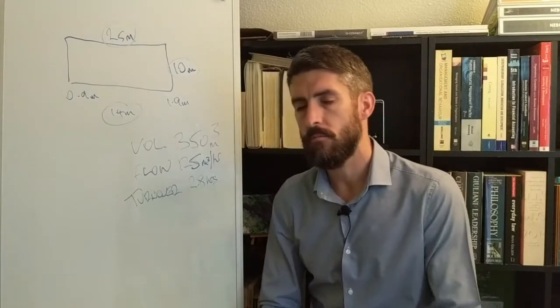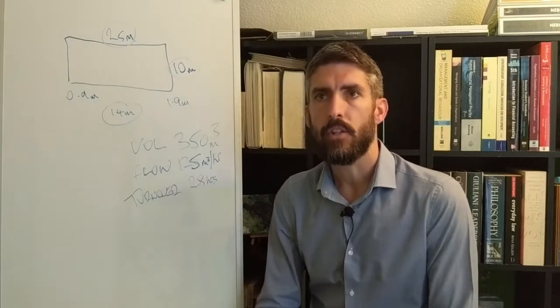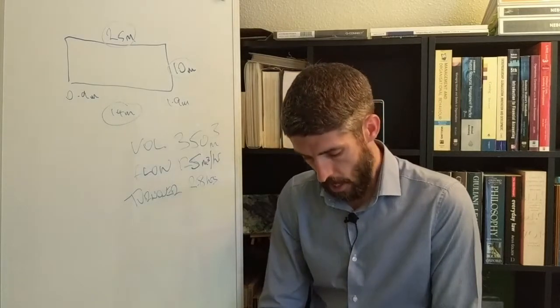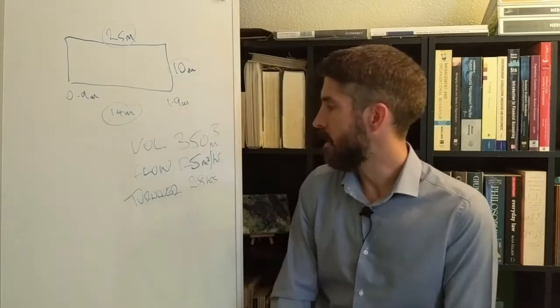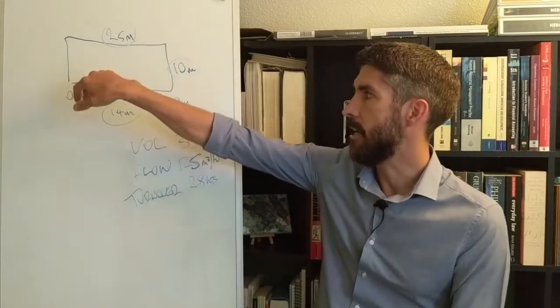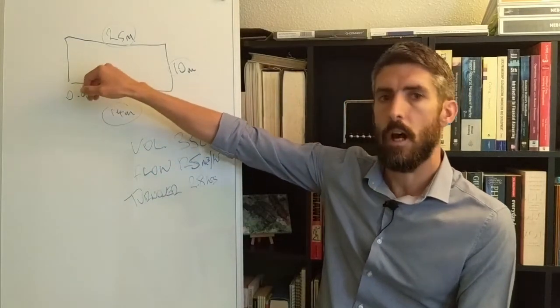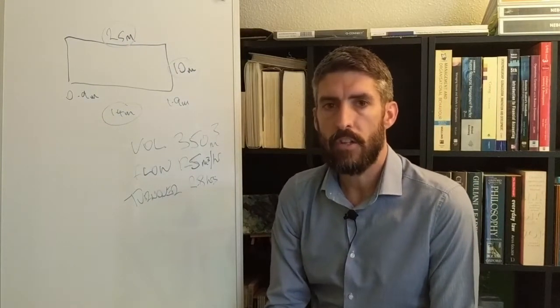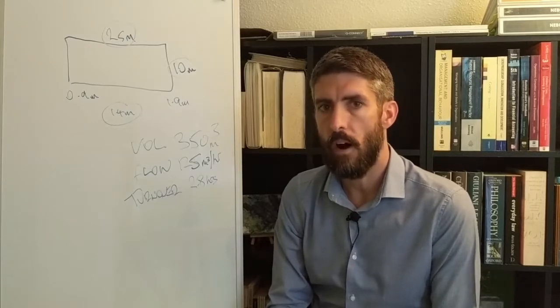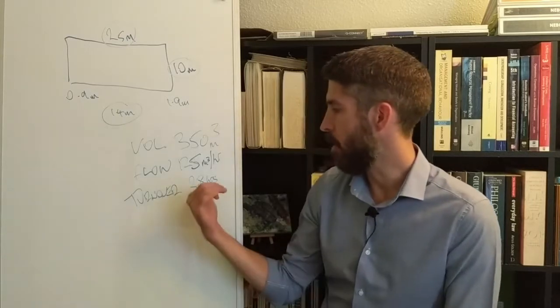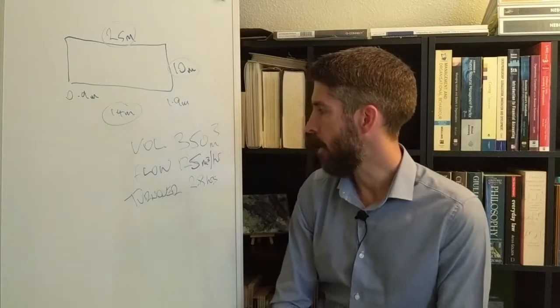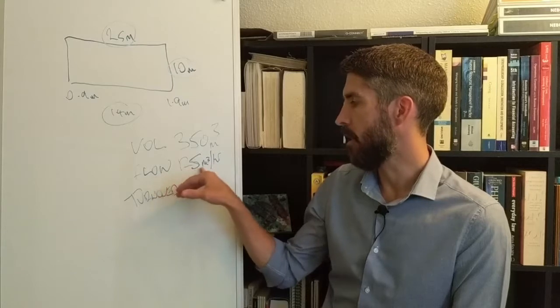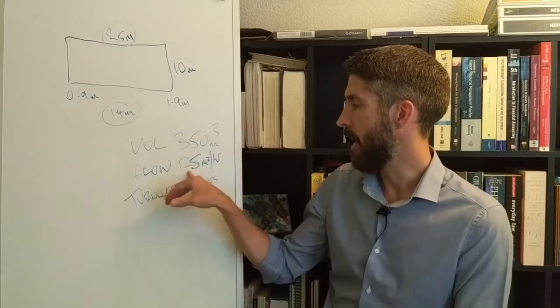So 2.8 hours, that's going to be two and three quarter hours, which is about right. Because like I said before, a pool of this type, a 25 meter pool, you'd expect that a recommended turnover time for that type of pool would be between 2.5 and three hours. So 2.8 would be within that range.